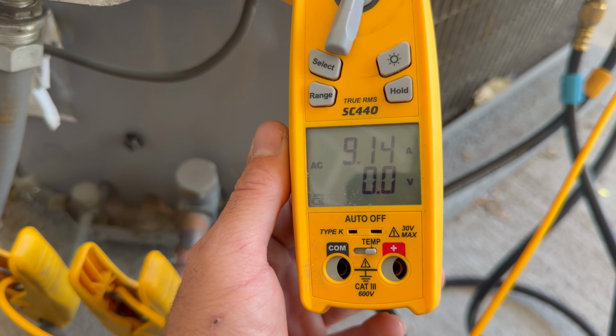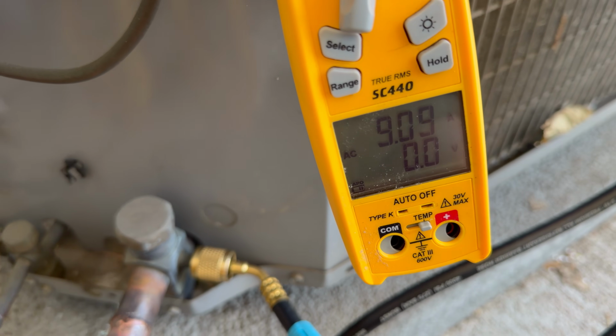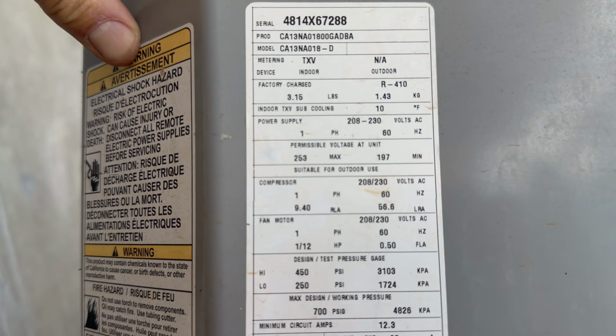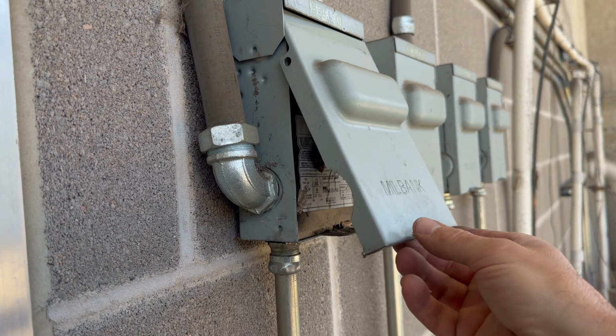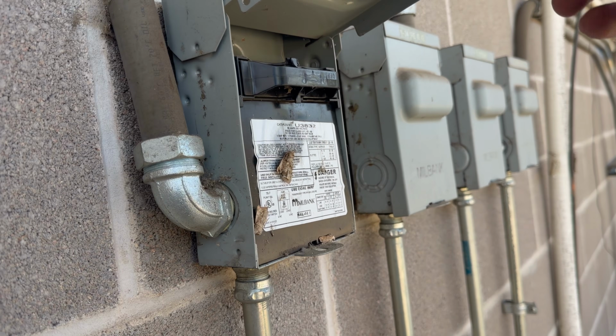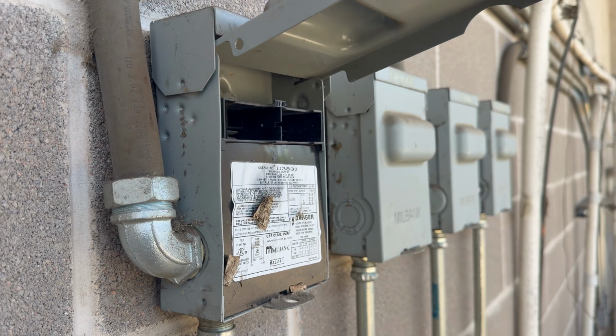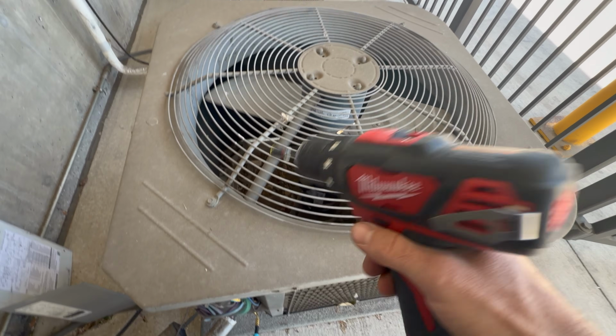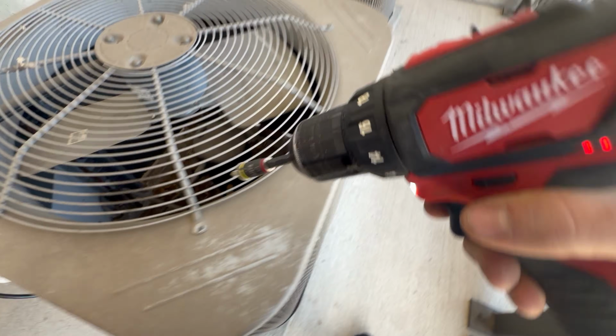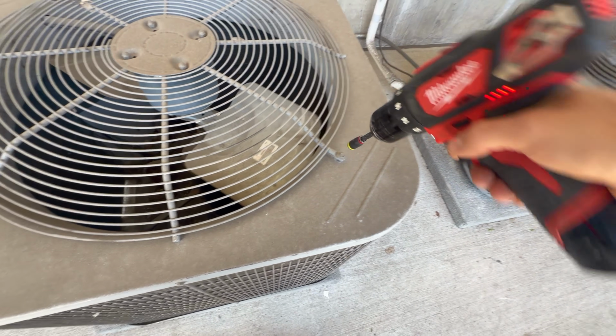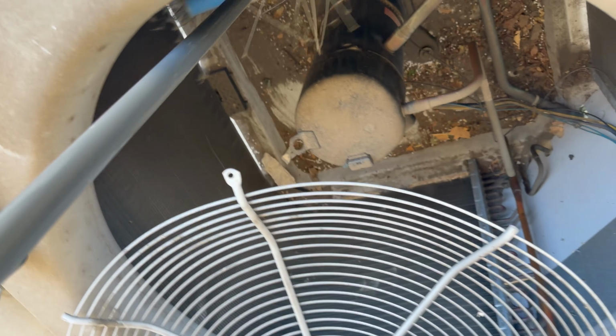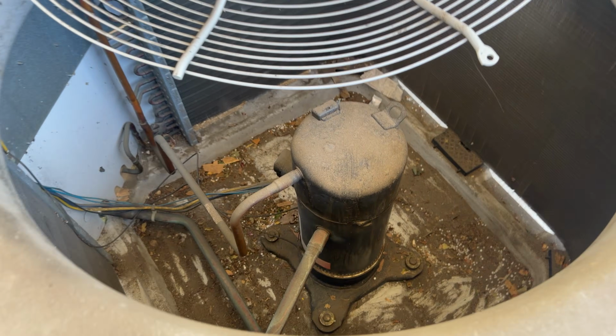Our compressor run amps are at 9.1, 9.25. They're kind of fluctuating a little bit. And our run load amps on the nameplate are 9.4. Gonna remove the high voltage power from the unit. I'm gonna remove the fan cover just because I want to get all these leaves and junk out. It is not completely necessary in every situation to remove the fan cover. Bulky stuff out of there.